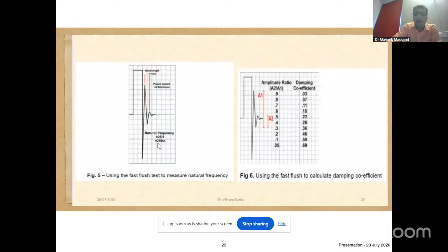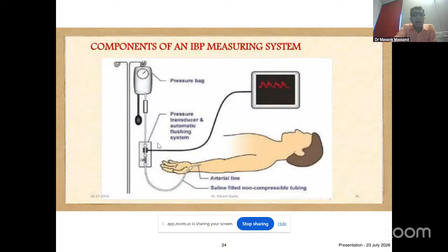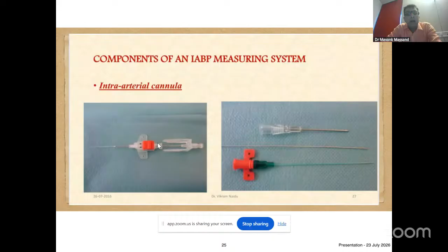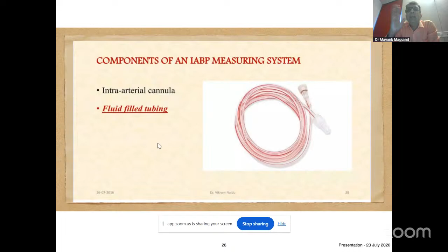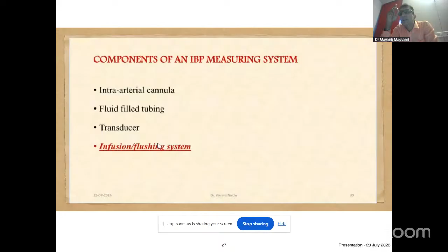Now, the components are a bottle with a pressure bag. Then from there, the liquid comes into the pressure transducer or automatic flushing system, from where the cable goes into the monitor, and another cable comes from the arterial line into the system. Now, this is one of the cannulas that is very important. This is based upon the Seldinger technique. This is based upon the cannula-over-stylet technique. This is another tube. As I said, this tubing before being attached should be completely free of air, so it is called the de-airing process, in order to limit air embolism into the system. Intra-arterial cannula, fluid-filled tubing, transducer, and there is a flushing system that is connected outside. Now, the signal processor, amplifier, and display are already there in the monitoring system.